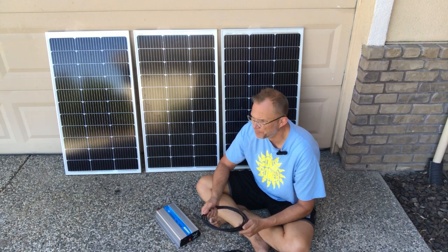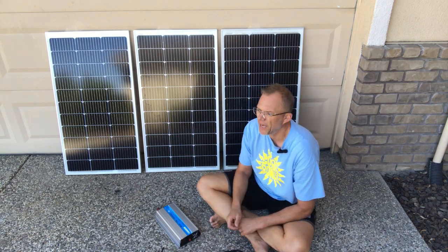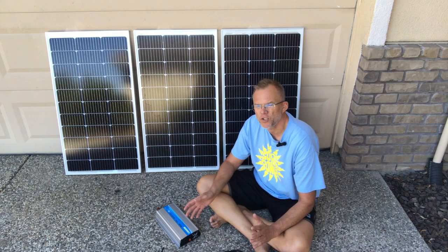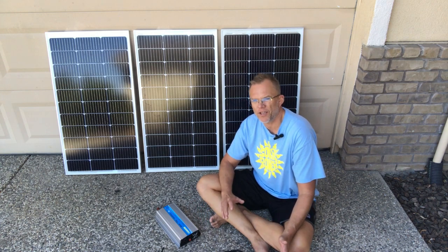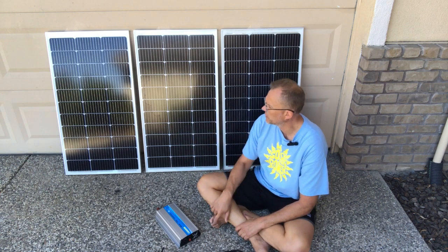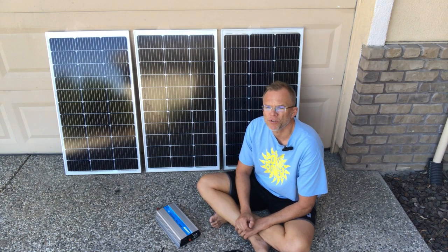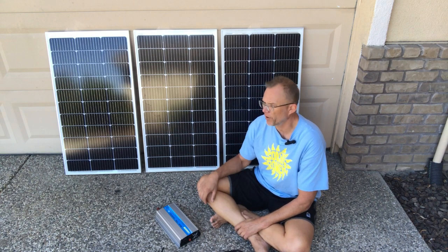The lower the number, the bigger the cable, the thicker the cable, and the thicker the cable, the further they can run. So when we are installing solar panels, I wouldn't say it's tricks, but there's certain things you can do to avoid needing longer cables. Let's say we have these 3 solar panels pushing up to 15 amps and we want to run them 40 feet.